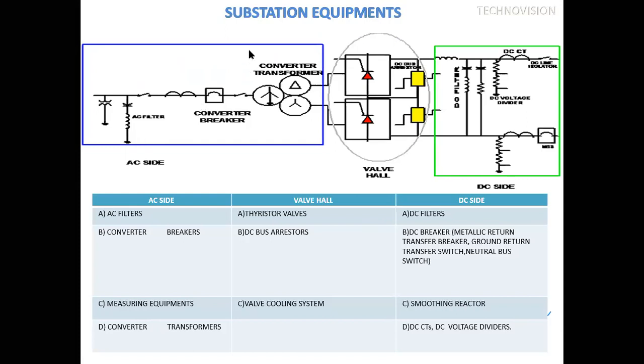Okay. So on the AC side, there are some equipments like AC filters, converter breakers, measuring equipments like conventional CTs and CVTs, and here converter transformers on the AC side. These are converter transformers, these are the converter breakers, these are the DC CTs, these are the isolators, these are AC filters, and this, we can say, is a CVT, capacitance voltage transformer. And in the middle there is a thyristor valve. It is a combination of 6 pulse converters. Generally 12 pulse converters are used in the plus minus 500 kV DC.